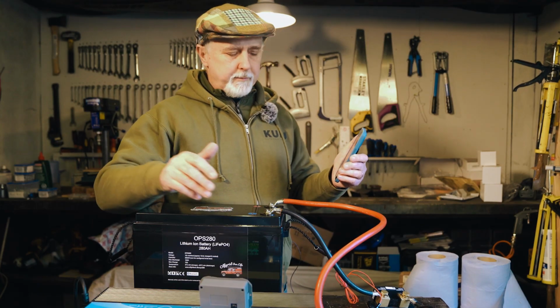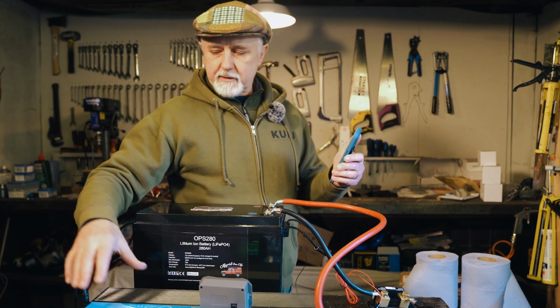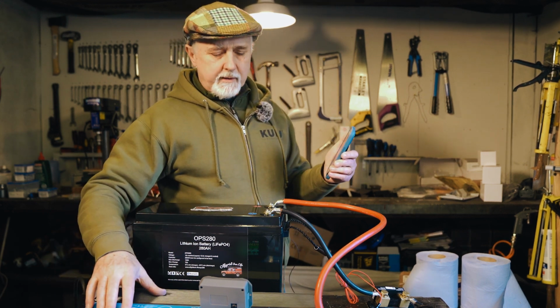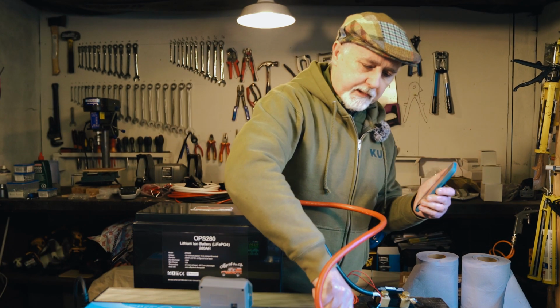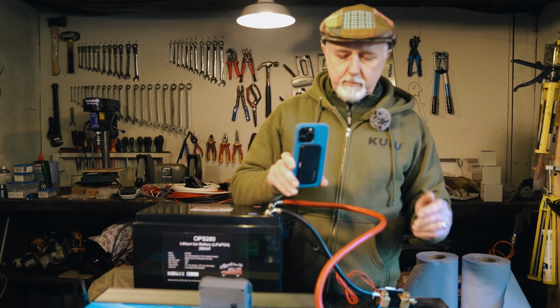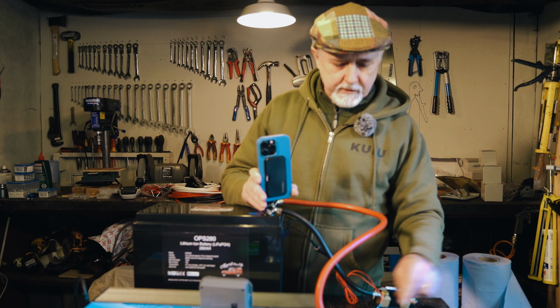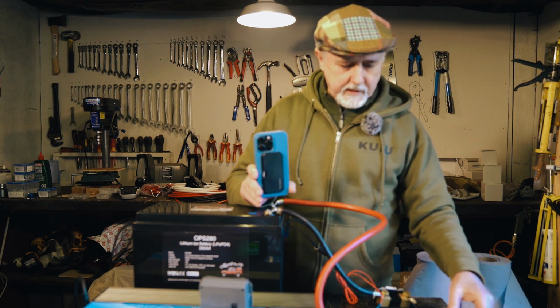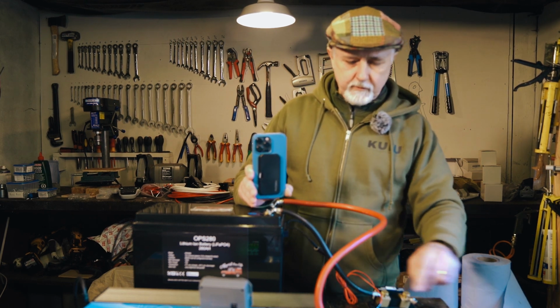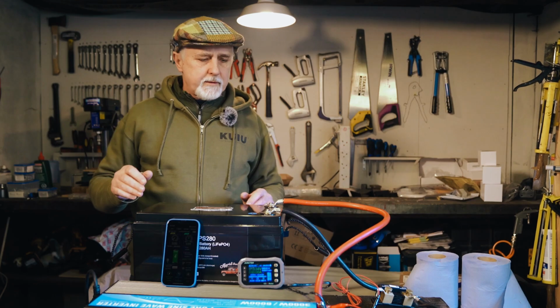So our next step is to plug a heater in, turn the inverter on, and get it running. But before that, I need to double check that all these cables are tight, because we don't want to build up too much heat at these points.